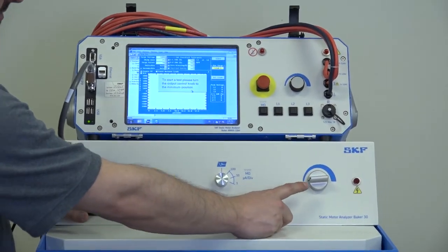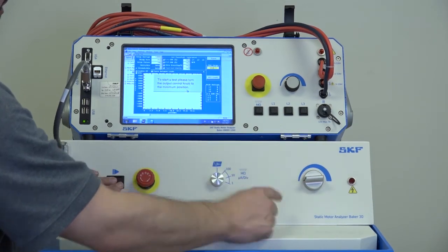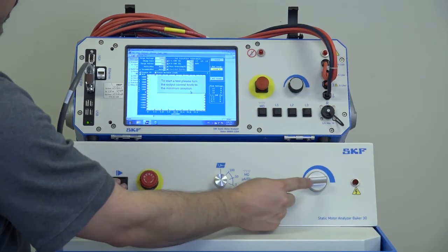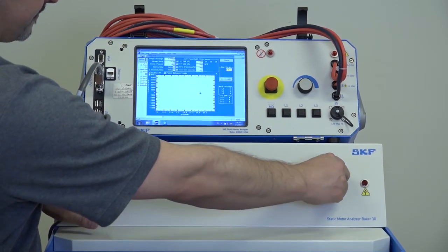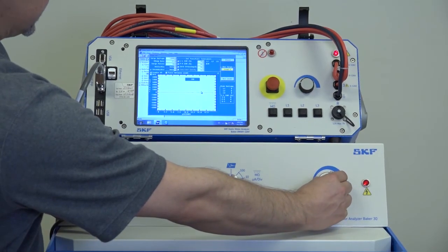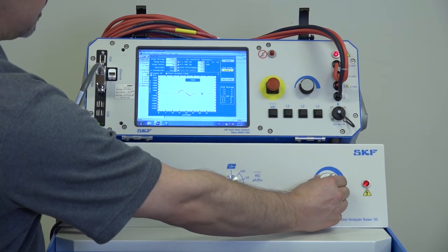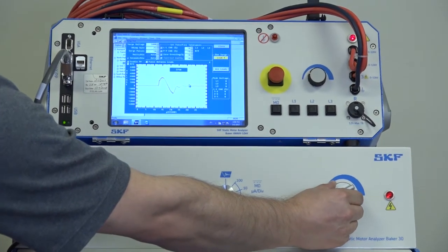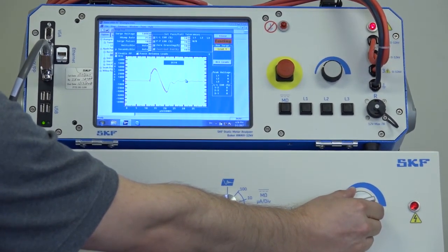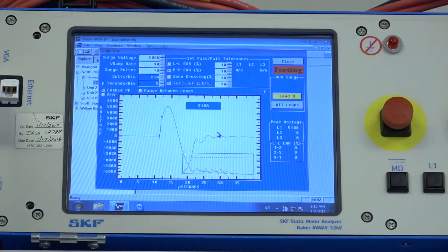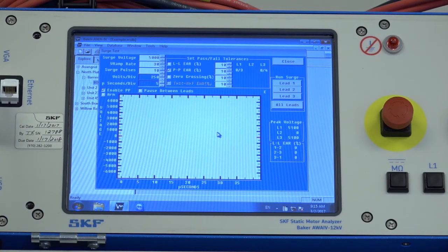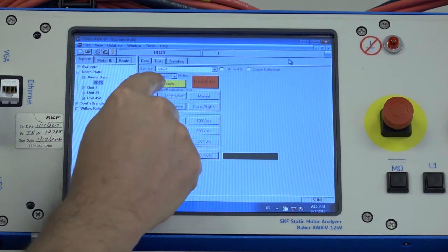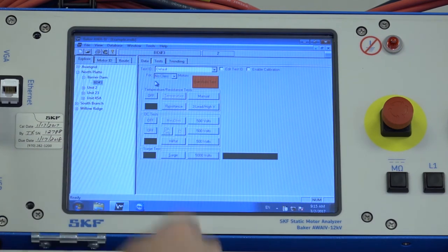Remember that the voltage control knob has to be all the way counterclockwise in the zero volts position, otherwise it won't initiate the test. It says to start a test, please turn the output control knob to the minimum position. Once we're at the minimum position, now we can increase the voltage and it'll auto scale the microseconds per division. We want to increase the voltage slowly until we achieve the appropriate test voltage. Now that we're completed with the test, we'll just hit close, and then we want to make sure we hit the save results button to save the test.